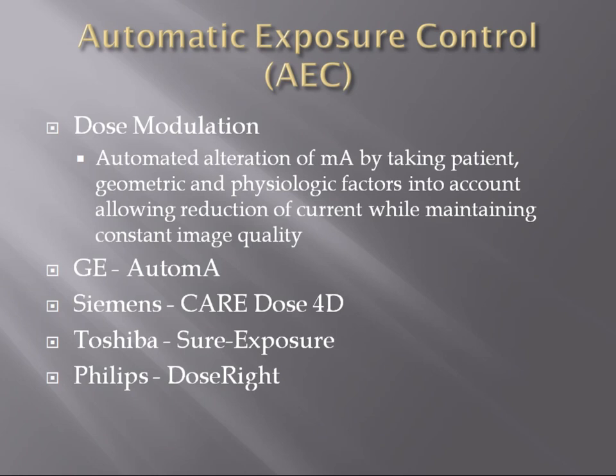We're talking about the scanner's ability to automatically change its dose — something referred to as automatic exposure control. We know automatic exposure control from conventional radiography, where a photo timer shuts off the camera once a photon threshold is reached. In CT, we use dose modulation — an automated alteration of the MA by taking patient, geometric, and physiologic factors into account, allowing reduction of current while maintaining constant image quality. Each vendor has their own name for it: GE has Auto mA, Siemens has CARE Dose 4D, Toshiba has Sure Exposure, and Philips has Dose Right — but all are forms of automatic exposure control or dose modulation.